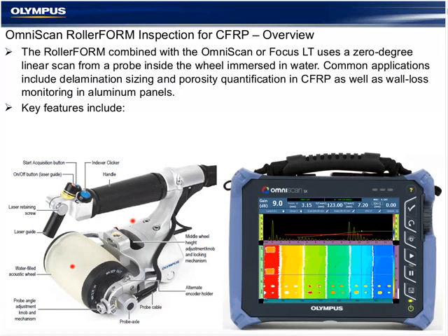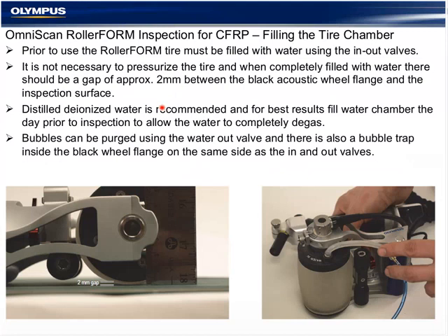The RollerFORM is an ergonomically designed, lightweight roller wheel probe that contains a phased array probe inside a water-filled tire chamber. It includes several mechanical adjustments that we'll be learning about. Key features include a specialized tire material impedance matched for water, and a specialized phased array probe that comes in several sizes, frequencies and designs we'll learn more about during the webinar. The wheel probe includes a laser guide system for accurate scanning and some integrated buttons that work with the OmniScan to make acquisitions fast and simple. It's a perfect companion to the OmniScan SX or MX2, and this presentation will take us through the setup of the OmniScan, the mechanical fine-tuning of the inspection, including the C-scans and acquisition.